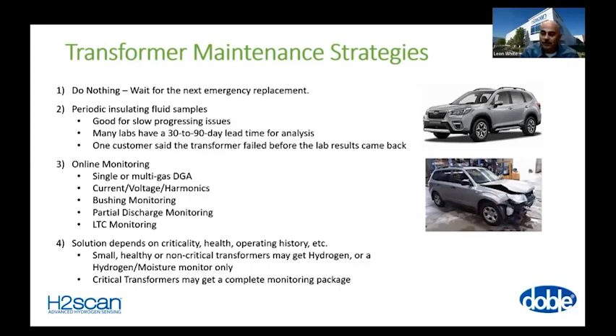If you're not treating your transformers properly, if you're not maintaining them, if you're not keeping the protection from letting the transformer see through faults, the more through faults, and especially the more significant through faults that they see, the less life you're likely to see from that transformer. So as Tony pointed out, through faults are a big issue, and protecting your transformers from through faults is very important. That goes back to Moses' presentation about making sure your protection schemes, your relaying and so forth, are properly maintained.